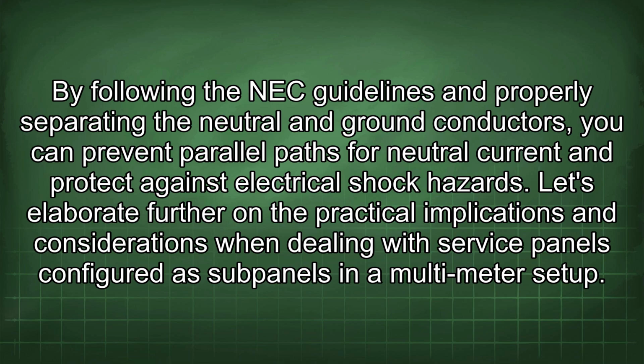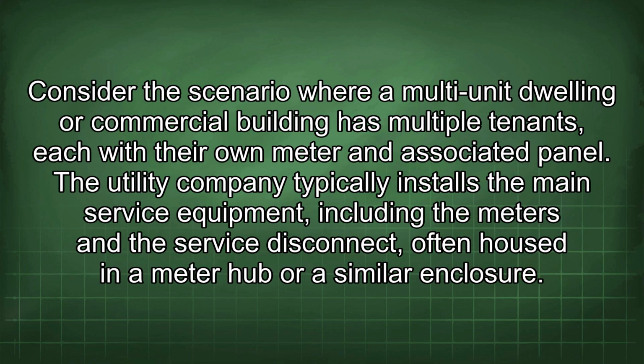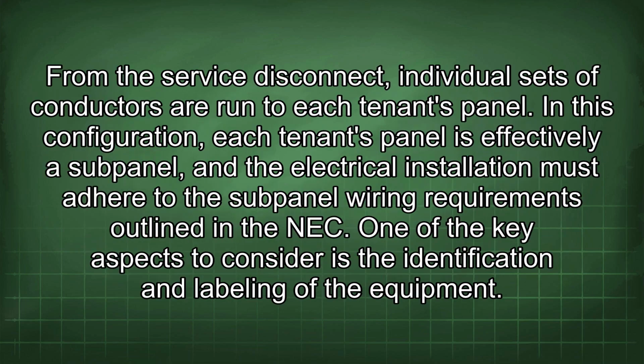Let's elaborate further on the practical implications and considerations when dealing with service panels configured as subpanels in a multi-meter setup. Consider the scenario where a multi-unit dwelling or commercial building has multiple tenants, each with their own meter and associated panel. The utility company typically installs the main service equipment, including the meters and the service disconnect, often housed in a meter hub or similar enclosure. From the service disconnect, individual sets of conductors are run to each tenant's panel. In this configuration, each tenant's panel is effectively a subpanel, and the electrical installation must adhere to the subpanel wiring requirements outlined in the NEC.